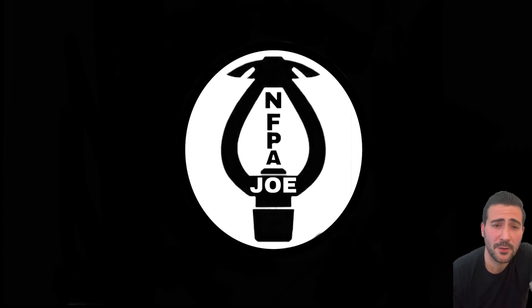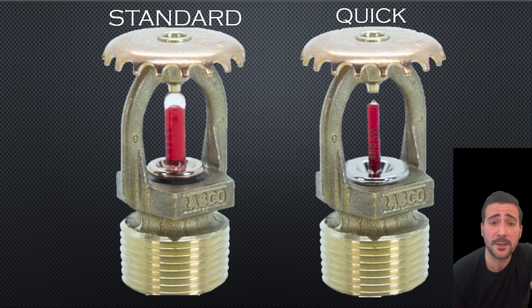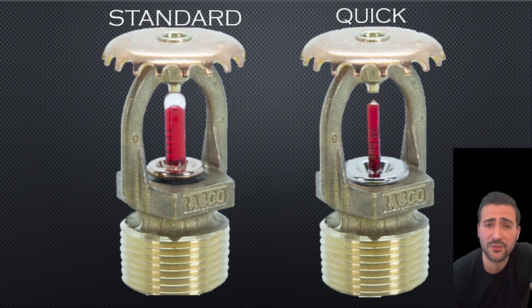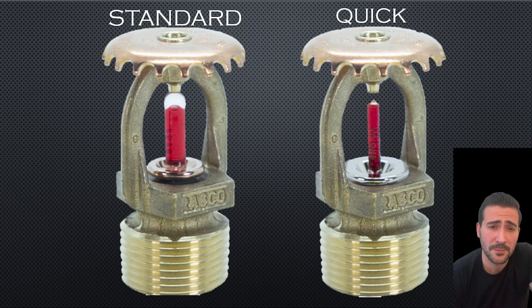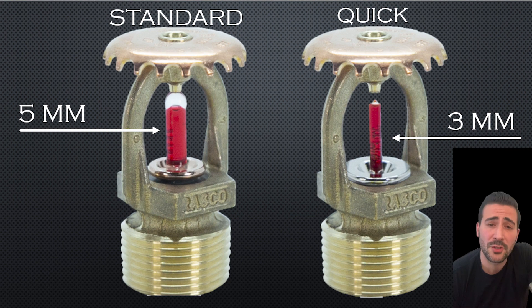This video is on the difference between the standard response and the quick response fire sprinkler head. Let's take a look at these two heads. If you notice two different sized bulbs — you are correct. We have two reliable standard spray uprights. Everything is the same except for the bulbs. The standard response utilizes a five millimeter bulb while the quick response utilizes a three millimeter bulb.